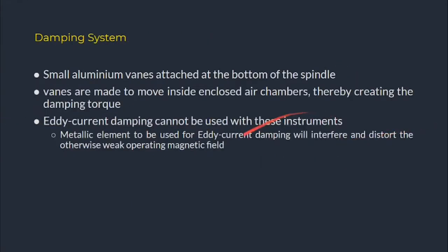For the damping system, small aluminium vanes attached at the bottom of the spindle are moved inside enclosed air chambers, thereby creating the damping torque. Eddy current damping cannot be used because the metal element required for eddy current damping would interfere and distort the otherwise weak operating magnetic field of the dynamometer type wattmeter. Hence a pneumatic type damping system is used.